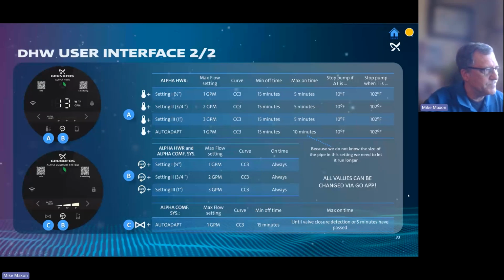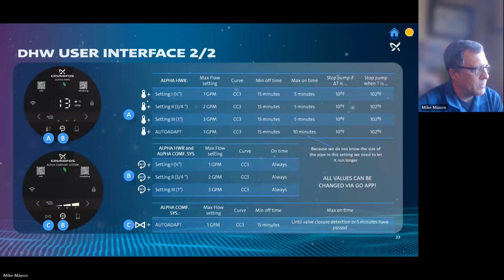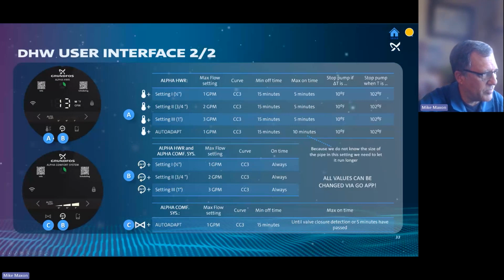So there's a lot here on this page. If you just use the front screen to set your settings and you use the temperature icon and you keep it in auto adapt, it's going to be at 1 gallon a minute. It's going to have a minimum off time of 15 minutes, maximum on time of 10 minutes. And it's going to look for a 10-degree temperature rise to turn the pump off. Now, again, that's using the screen here. If you go into the app, every one of these numbers here you could change. You could modify them to whatever your application is. If you set it for half inch pipe, you're still gonna get the 1 gallon a minute. Now we're gonna have 5-minute max on time. And you can see the difference here otherwise is the flow rate.